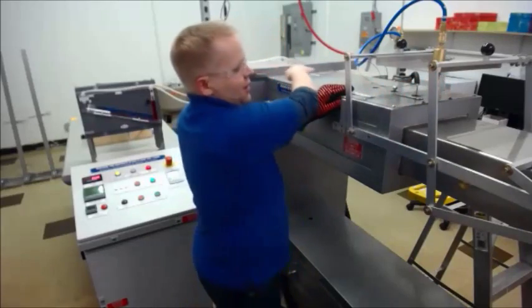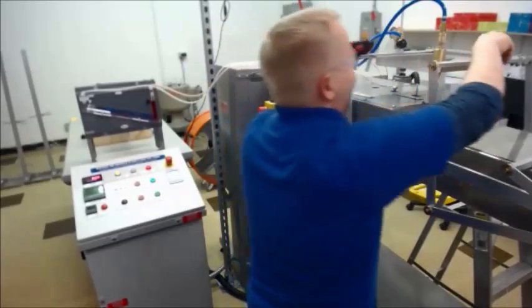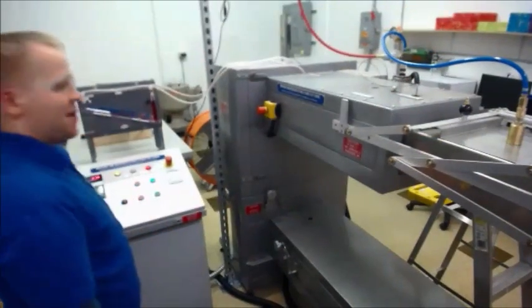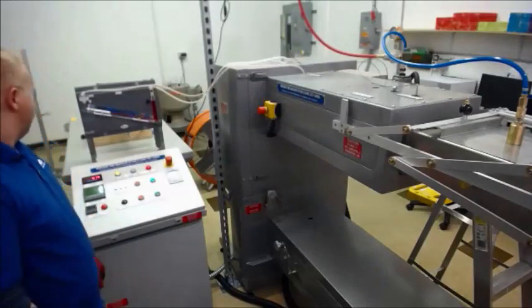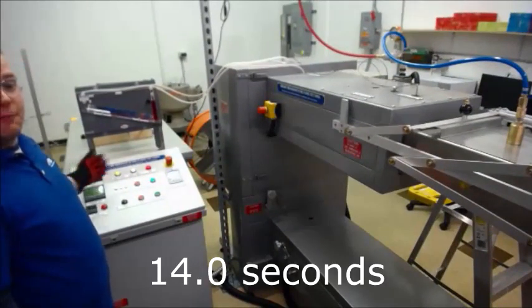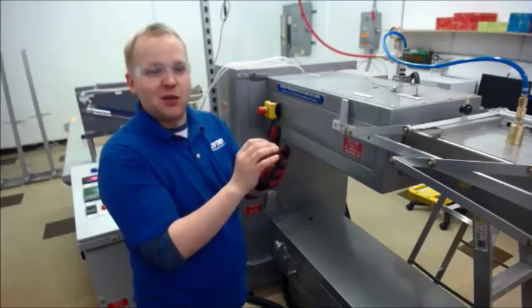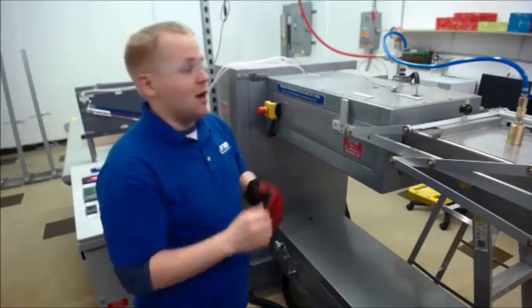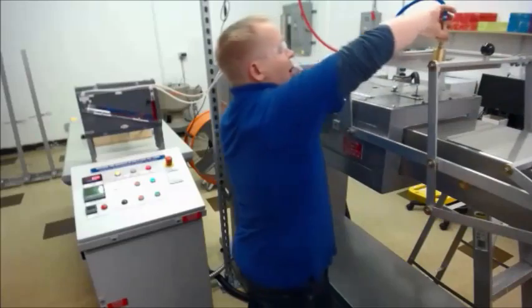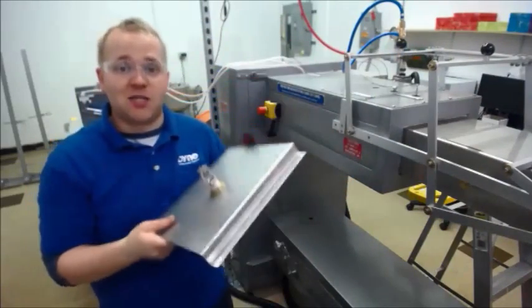This dust bunny is kind of on the backside, so when I test into the airflow, it's going to show that insulation effect. I positioned it so the airflow is going to hit that dust bunny first instead of the release mechanism. Only 14 seconds there. This could be a situation where the dust bunny just wasn't covering enough — it might not have had a lot of coverage. What we're seeing with this small amount of dust bunny though is that even that is enough to possibly affect the result.